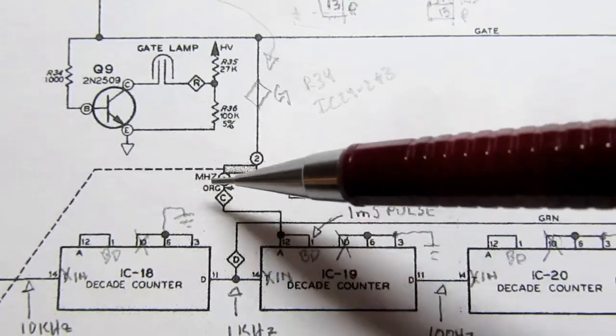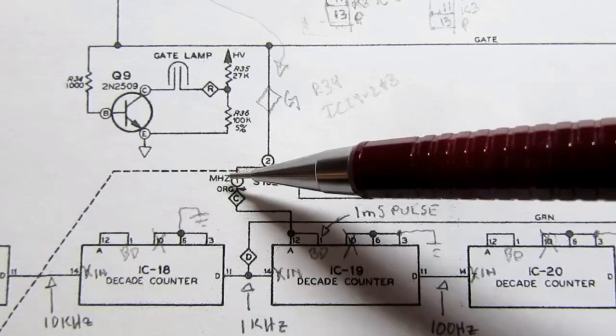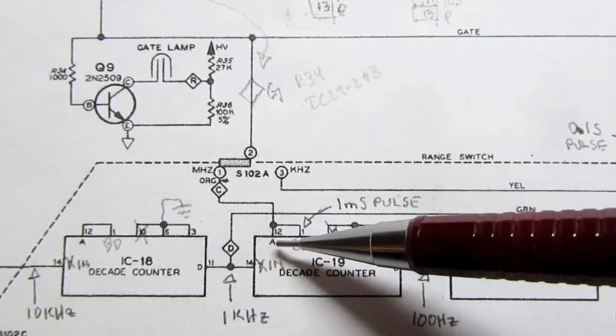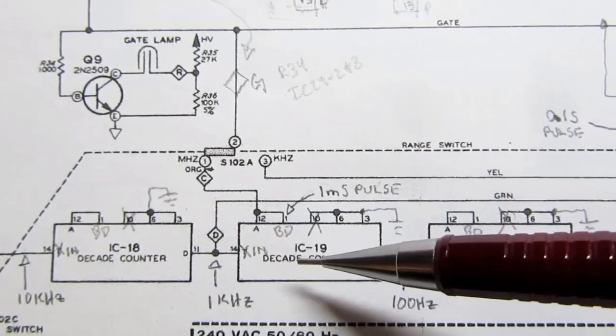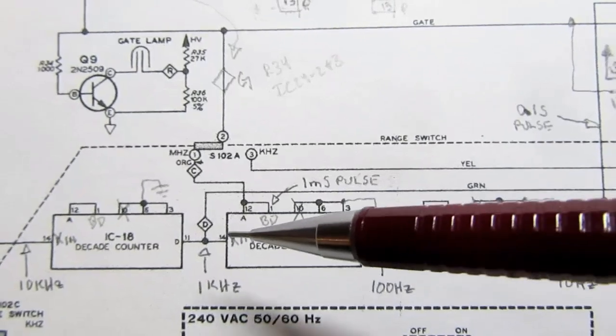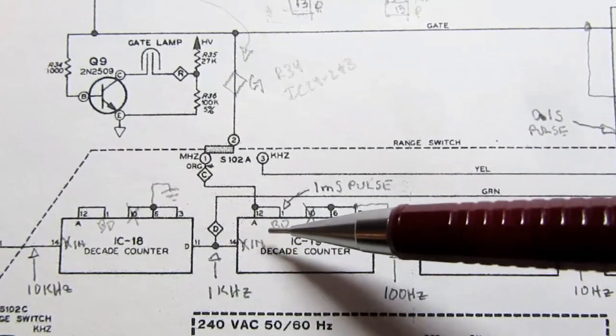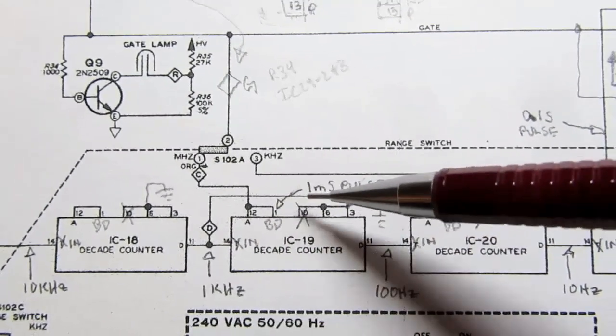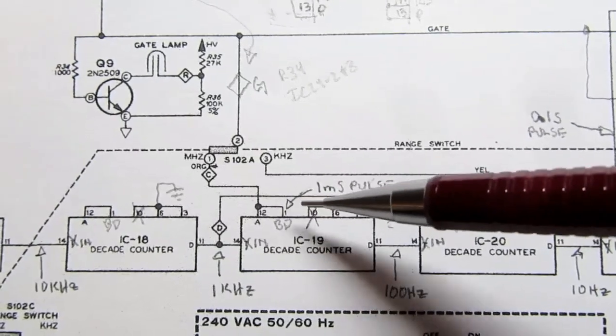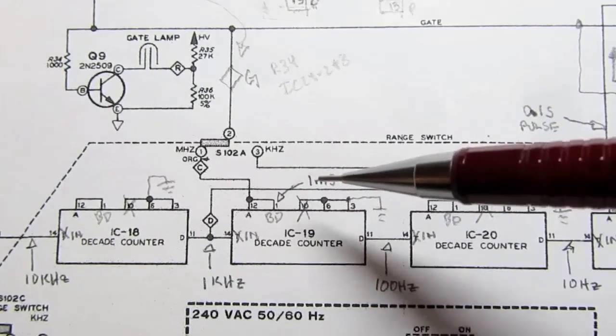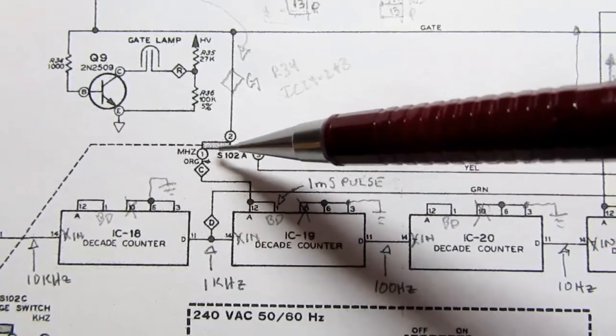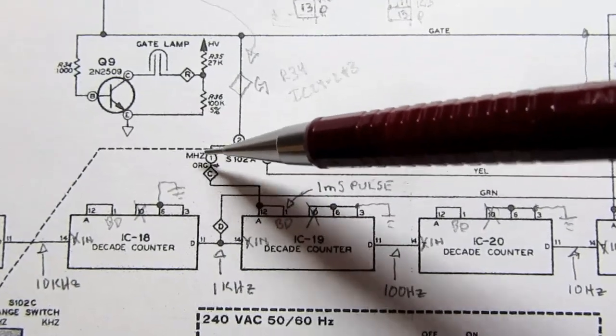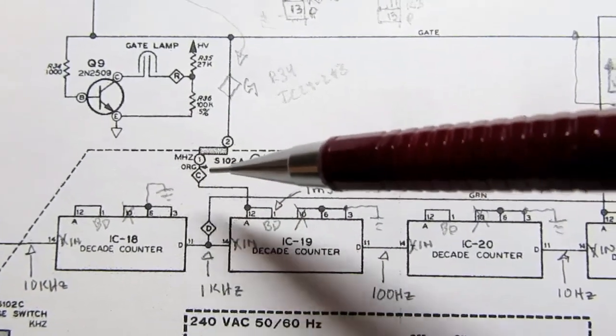And here's the switch. In megahertz, we tap off the A output of this decade counter. So just think of it as this divided by 2, and then using half of that, because we're only looking at half the waveform when it's logically high, for example. So that gives us our 1 millisecond gate for the megahertz range or mode.